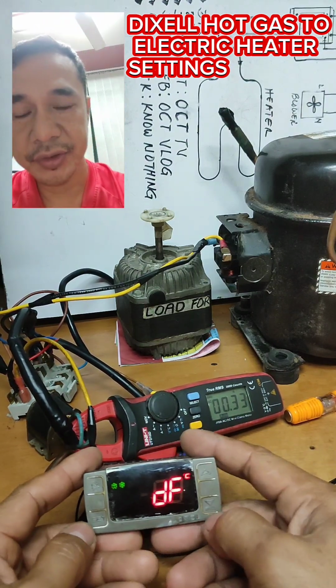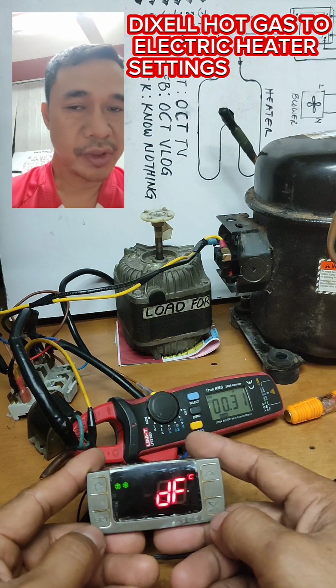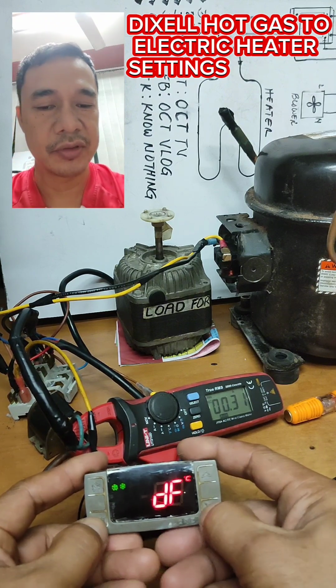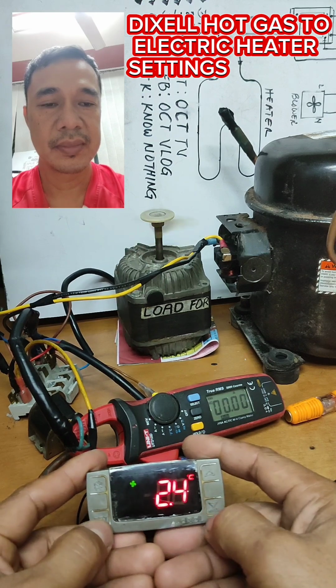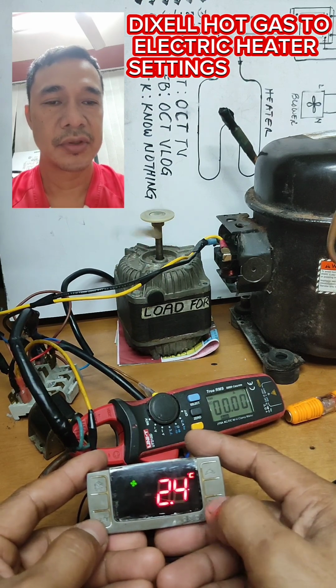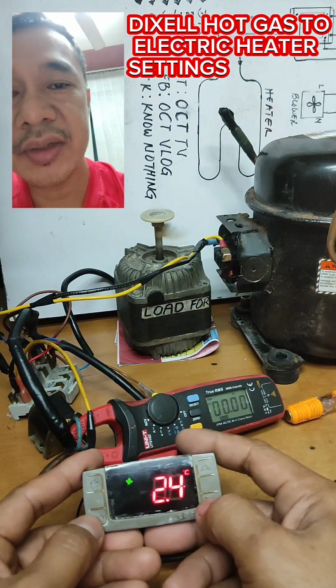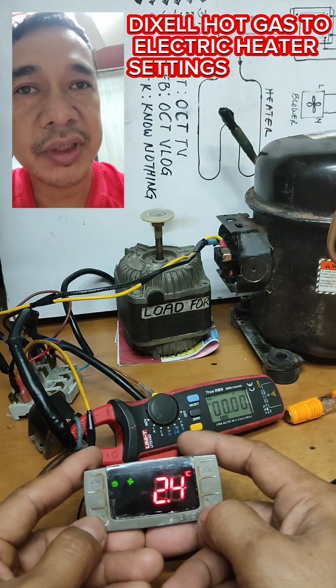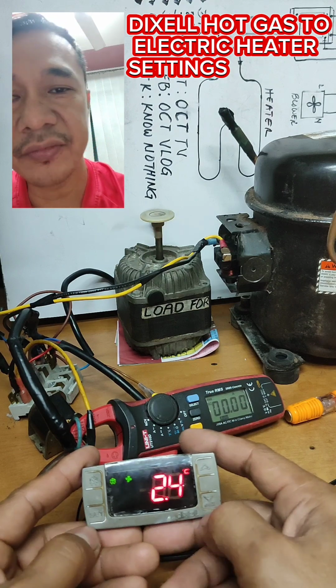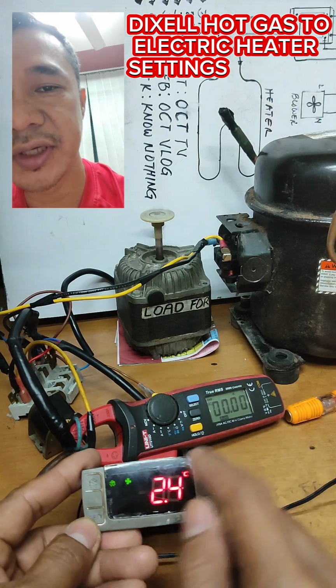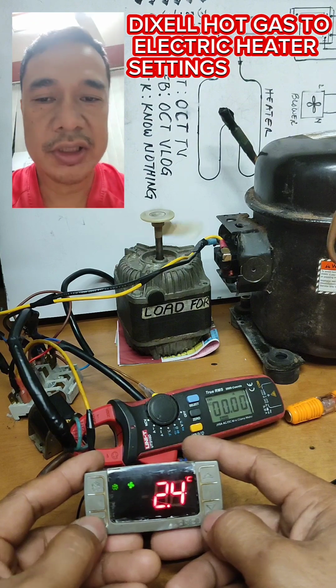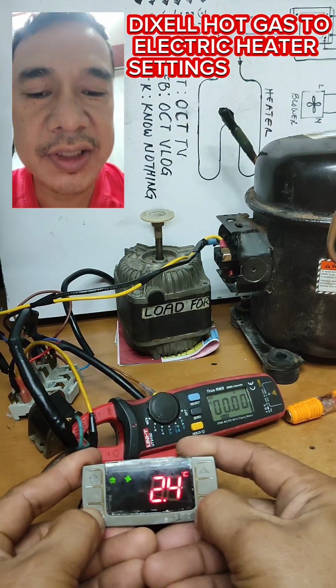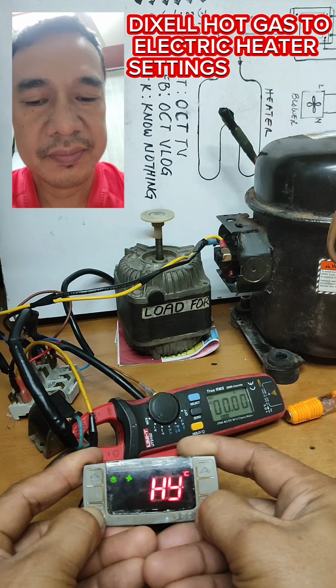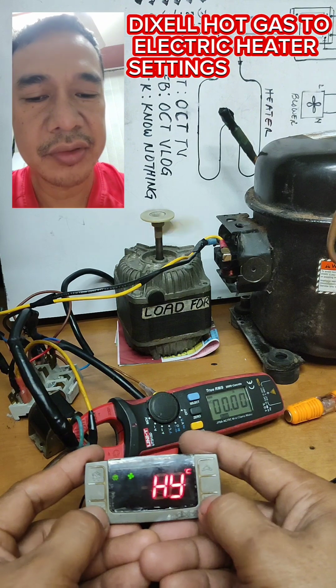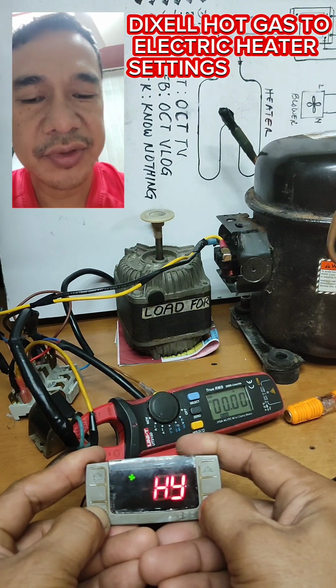To do that, we are going to enter the parameter here. Press the set button and hold it down for 3 seconds. Okay, the defrost is done because I set it to 1 minute for the MDF. Okay, let's continue, guys. This is now the tripping time. Let's press the set button and hold it down for 3 seconds, and another set button and hold it down for 7 seconds to enter the hidden parameter.